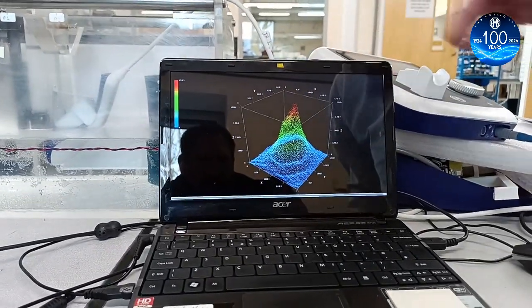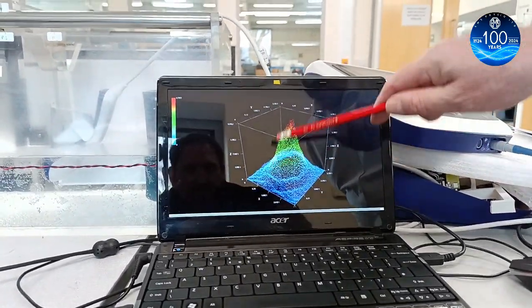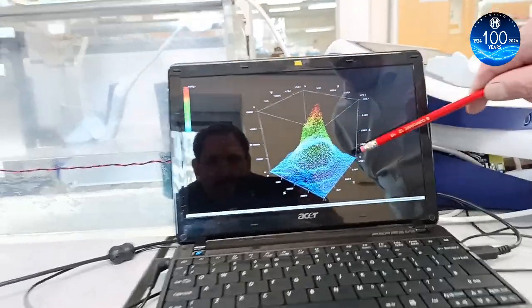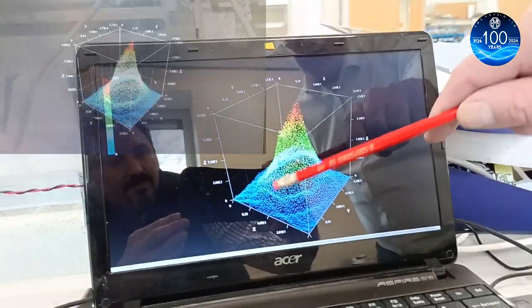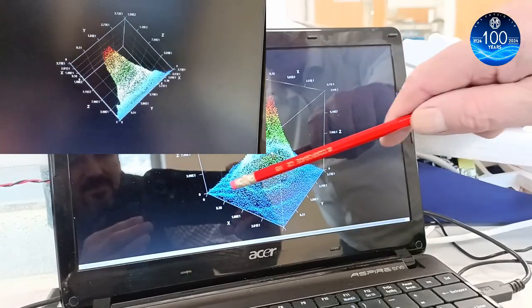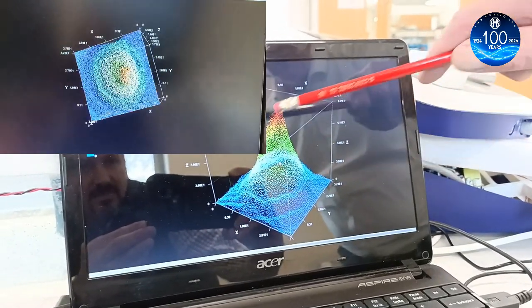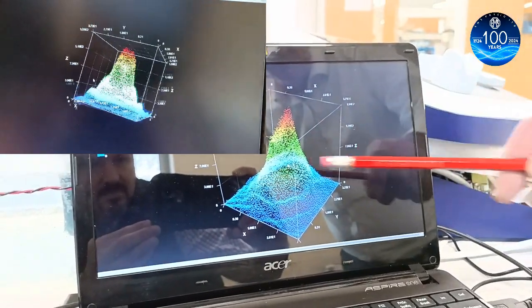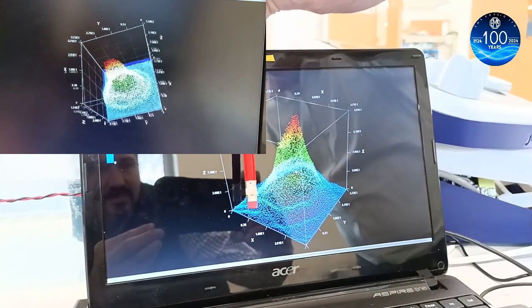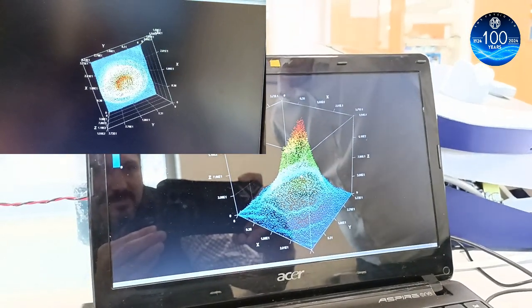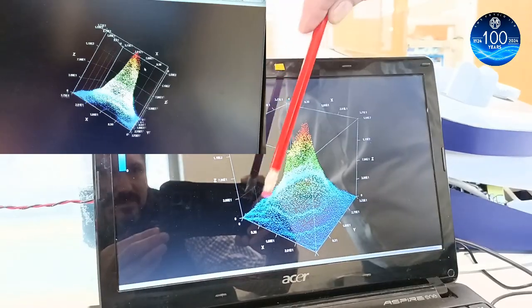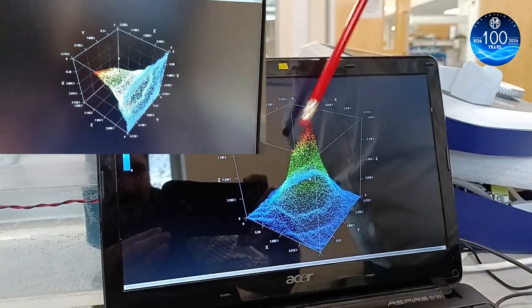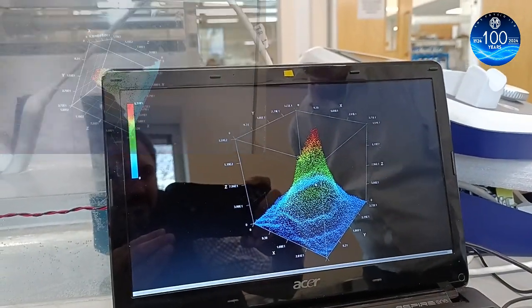we can use the data that we've gathered to present a three-dimensional graphical illustration of the output from the transducer, which shows that we've got a nice uniform wave there. What you don't want to see is one that is skewed to one side or very tall and thin, which would indicate a hot spot in the middle. So this is a nice uniform distribution of the power over the entire front face of the transducer.